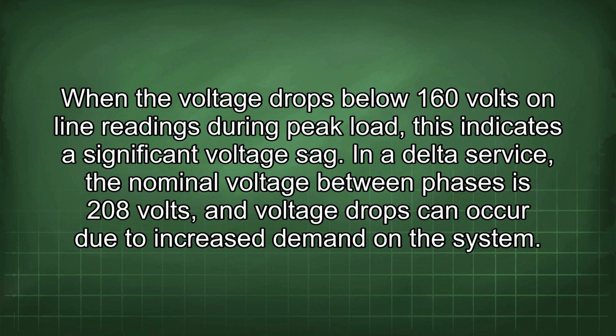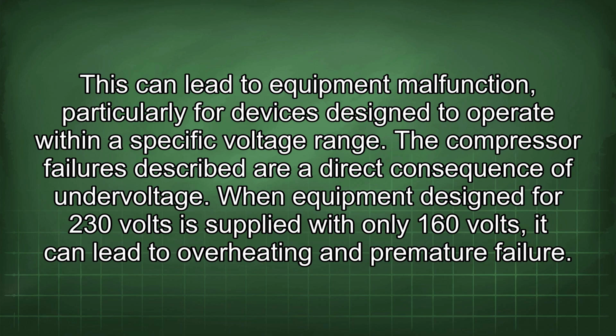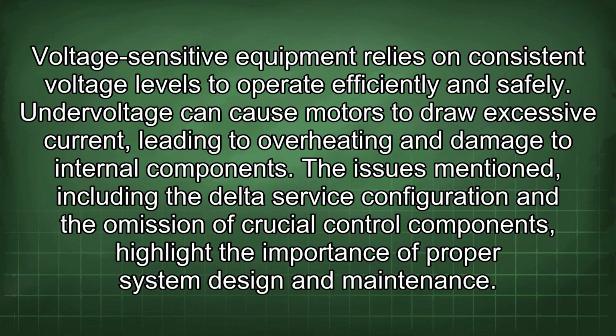When the voltage drops below 160 volts on line readings during peak load, this indicates a significant voltage sag. In a delta service, the nominal voltage between phases is 208 volts, and voltage drops can occur due to increased demand in the system. This can lead to equipment malfunction, particularly for devices designed to operate within a specific voltage range. The compressor failures described are a direct consequence of undervoltage. Where equipment designed for 230 volts is supplied with only 160 volts, it can lead to overheating and premature failure. Voltage-sensitive equipment relies on consistent voltage levels to operate efficiently and safely. Undervoltage can cause motors to draw excessive current, leading to overheating and damage to internal components.